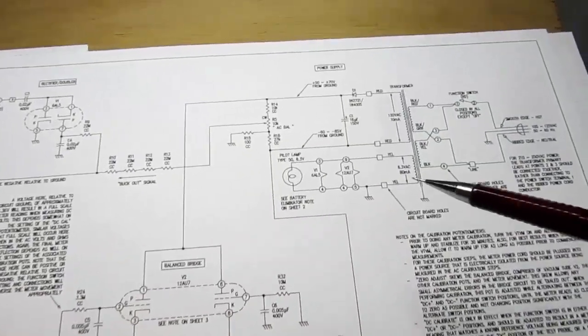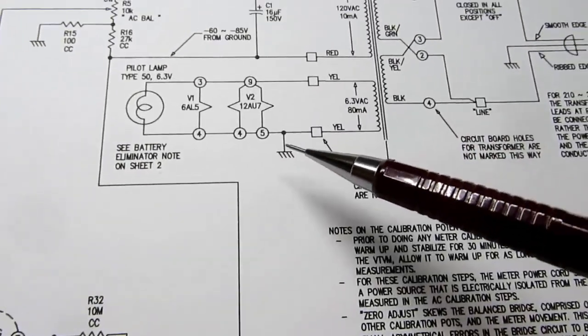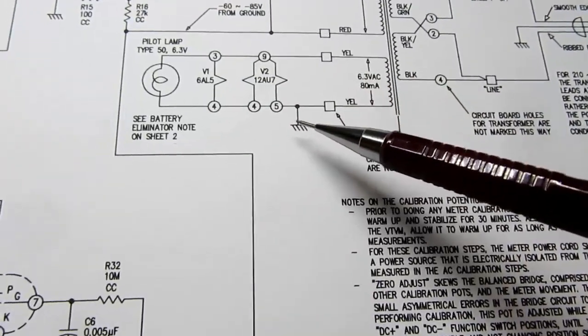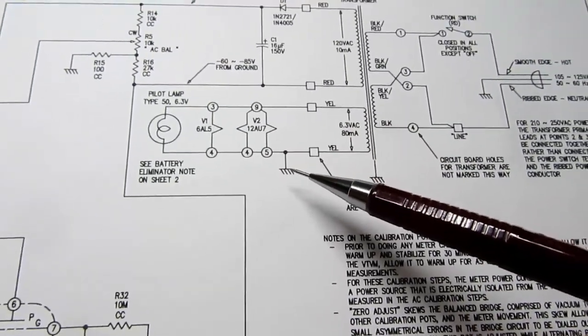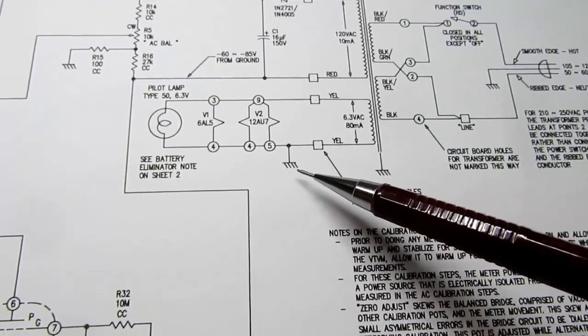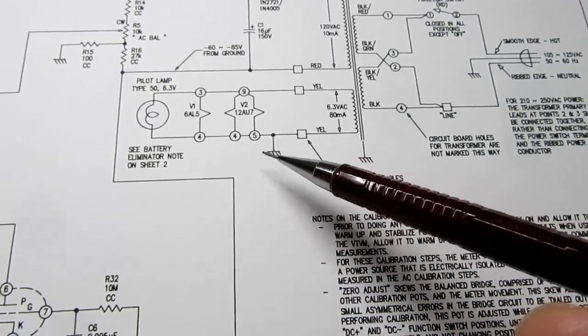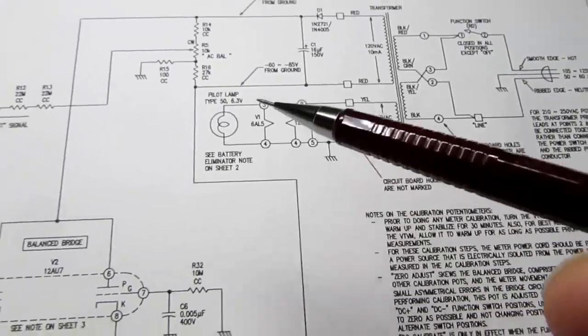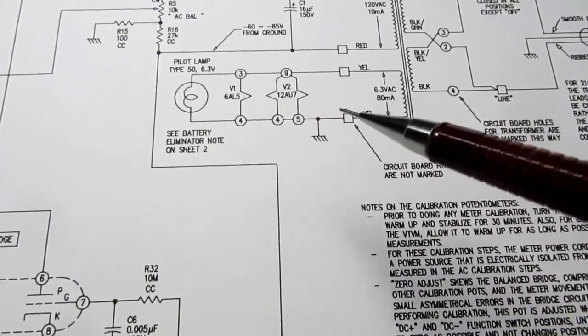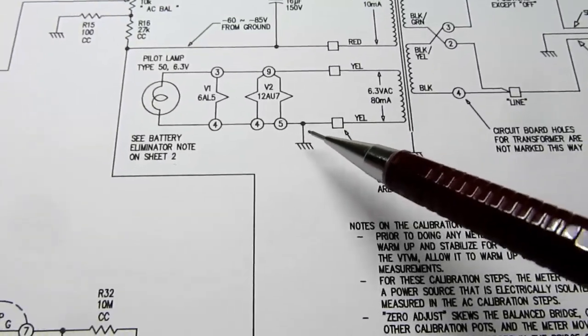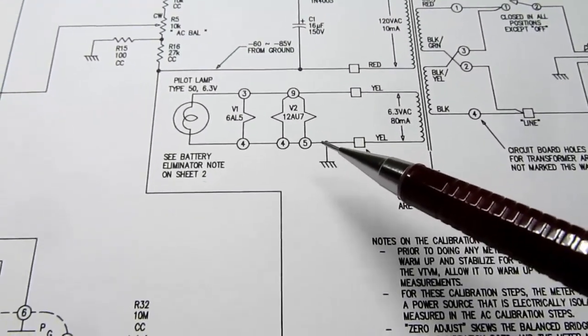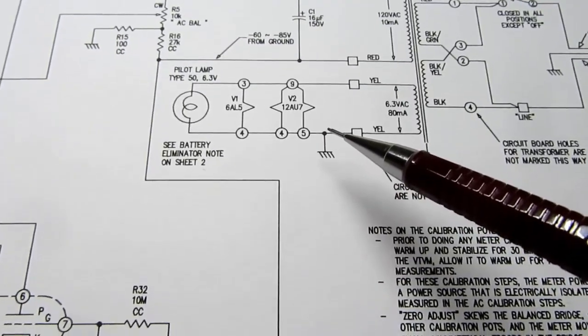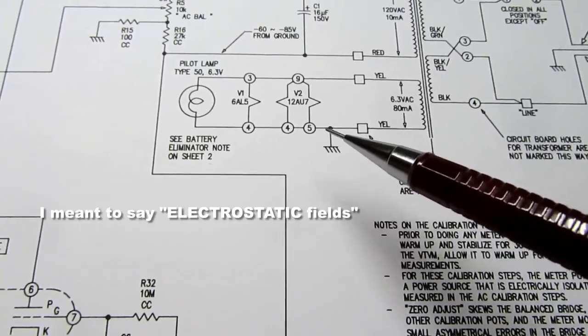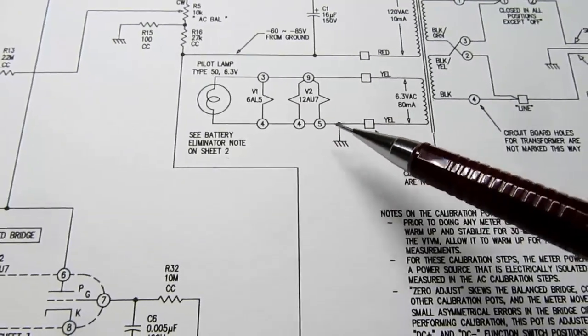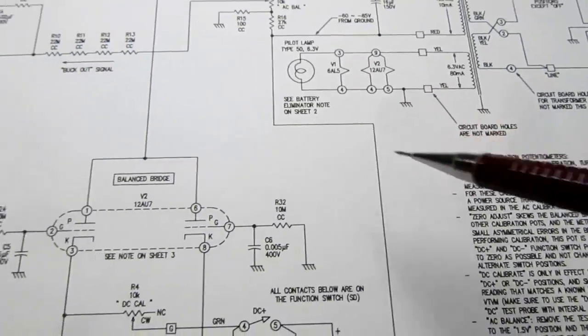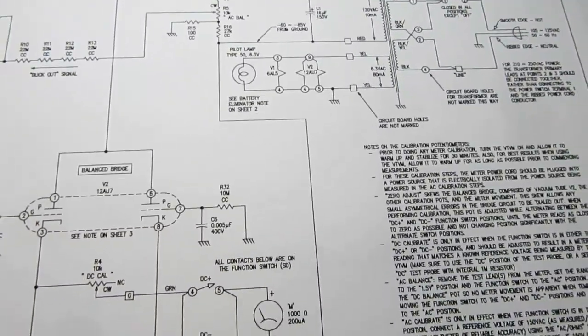Somebody might ask, why is one side of this filament circuit connected to circuit ground? Why does it have to be? Well, apparently the answer is that it does not have to be. If you remove this ground reference here, the meter would still work. But this is a trick that they found out, that it makes the meter less susceptible to interference and electrostatic fields and things if one side of this is connected to ground.